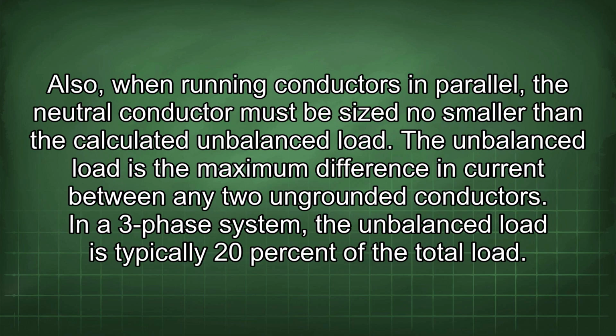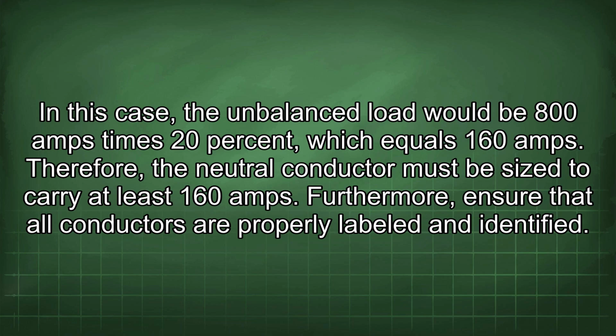Also, when running conductors in parallel, the neutral conductor must be sized no smaller than the calculated unbalanced load. The unbalanced load is the maximum difference in current between any two ungrounded conductors. In a 3-phase system, the unbalanced load is typically 20% of the total load. In this case, the unbalanced load would be 800 amps times 20%, which equals 160 amps. Therefore, the neutral conductor must be sized to carry at least 160 amps.